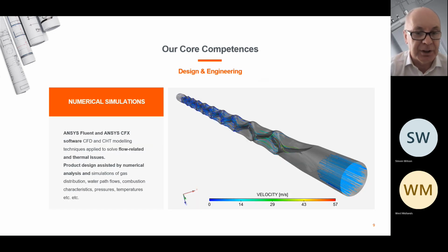If you look here, you can see a graphic from it where the flue gases are going down through the heat exchanger. This heat exchanger tube is formed from a flat sheet of stainless steel. It's then formed into a tube, and then it's pressed, maximising the efficiency of the heat exchanger.